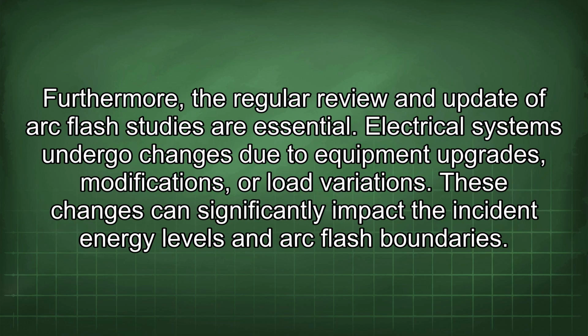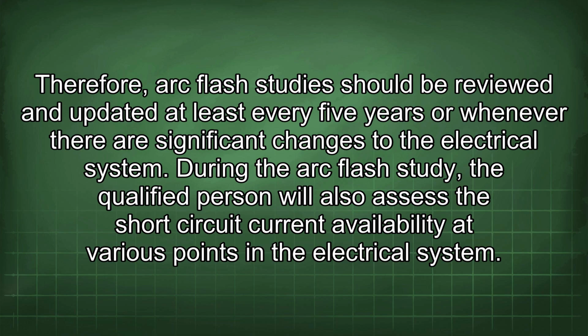Furthermore, the regular review and update of arc flash studies are essential. Electrical systems undergo changes due to equipment upgrades, modifications, or load variations. These changes can significantly impact the incident energy levels and arc flash boundaries. Therefore, arc flash studies should be reviewed and updated at least every 5 years or whenever there are significant changes to the electrical system.